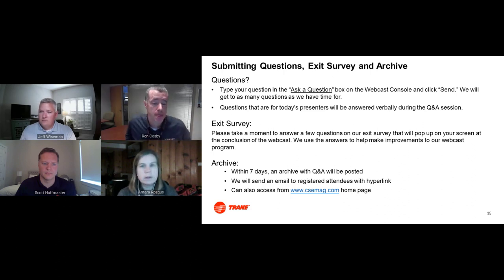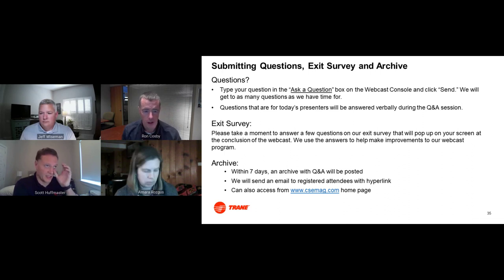All right, Scott, the next question is for you. Could the sensible cooling terminal units be considered to be providing simultaneous heating and cooling, which would be a violation of the energy code? Can you talk a little bit about that? So, yeah, sensible terminal unit works similarly to any other system where you've got the system separated. So what do I mean there? The energy code about energy recovery is really more focused on, let's say, a rooftop unit and the need to recapture heat for hot gas reheat, as opposed to relying fully on terminal heating.